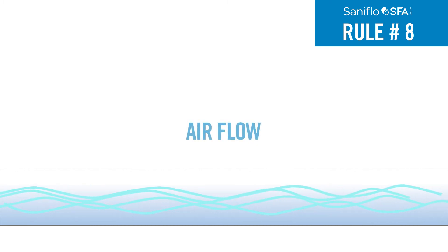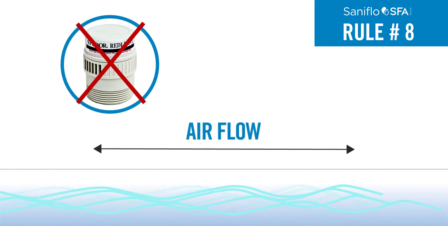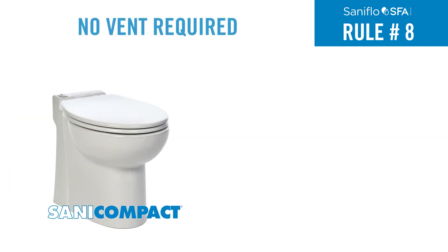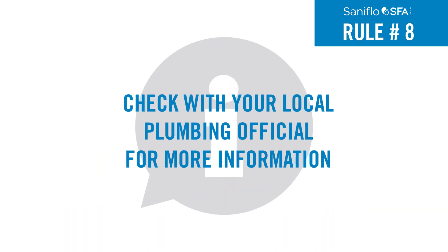Rule 8: Ensure that air flows freely in both directions for proper venting. Do not use one-way mechanical or Studor vents as these restrict airflow. Neither the Sani Compact nor the SaniStar need external vents as both have internal ones. Check with your local plumbing official for more information.